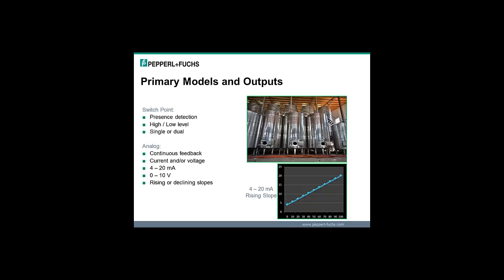Equally as popular for ultrasonics is the analog type. And here you get continuous feedback. So it's not just is the target there, is the target not there. It's giving you an increment. How close? Is it 4 millimeters away, 5 millimeters away, 6 millimeters away? So you get a continuous feedback. And that's either in an analog 4 to 20 milliamp or 0 to 10 volt output. And that can also be inverted. So some customers like it 20 to 4 and 10 to 0. You can do that as well.